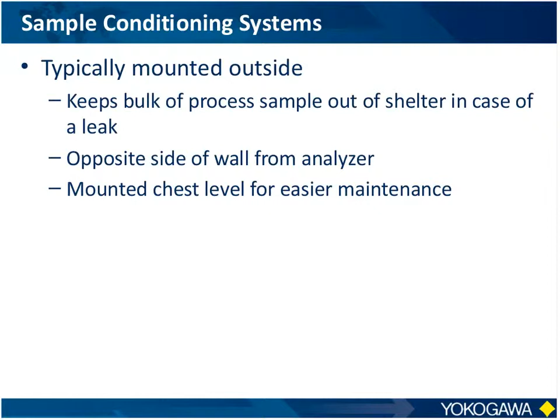One topic I want to spend just a couple seconds on here is the sample conditioning system. I kind of mentioned a little bit earlier that sample systems are a big part of analyzer system packages because what ends up happening, most analyzers that need packaging are extractive by nature. In other words, they take the sample out of the process to the analyzer where it needs to be temperature and pressure and flow and filtered so it's compatible to the analyzer and doesn't cause a lot of headaches. So all of that needs to be done as part of the design. And as I showed in earlier pictures, typically sample systems are mounted on panels or boxes on the outside of the shelter. And this, again, is to keep it so if there is a leak or such as that, it leaks on the outside of the shelter and not on the inside to keep it safe.